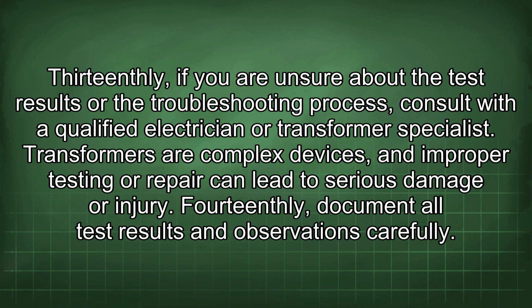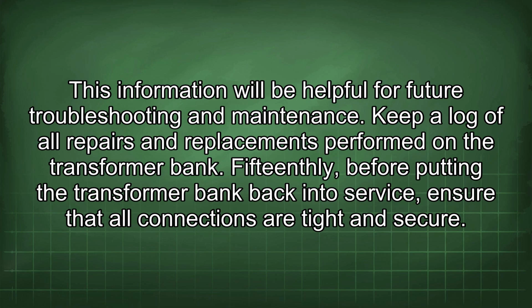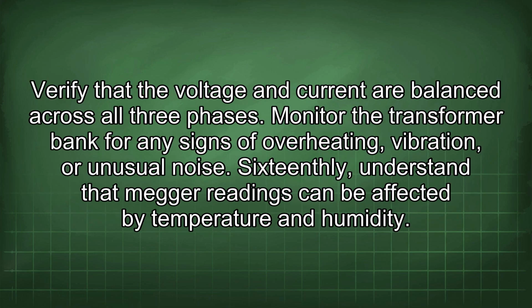14thly, document all test results and observations carefully. This information will be helpful for future troubleshooting and maintenance. Keep a log of all repairs and replacements performed on the transformer bank. 15thly, before putting the transformer bank back into service, ensure that all connections are tight and secure. Verify that the voltage and current are balanced across all three phases. Monitor the transformer bank for any signs of overheating, vibration, or unusual noise. 16thly, understand that megger readings can be affected by temperature and humidity.